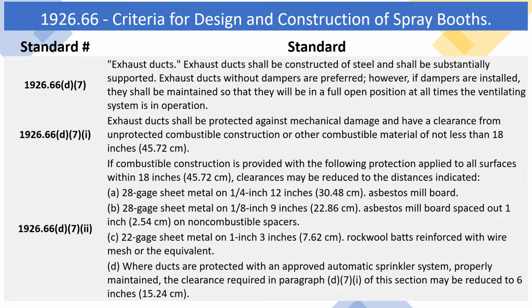1926.66(d)(7)(i) Exhaust ducts shall be protected against mechanical damage and have a clearance from unprotected combustible construction or other combustible material of not less than 18 inches (45.72 centimeters). 1926.66(d)(7)(ii) If combustible construction is provided with the following protection applied to all surfaces within 18 inches (45.72 centimeters), clearances may be reduced to the distances indicated.